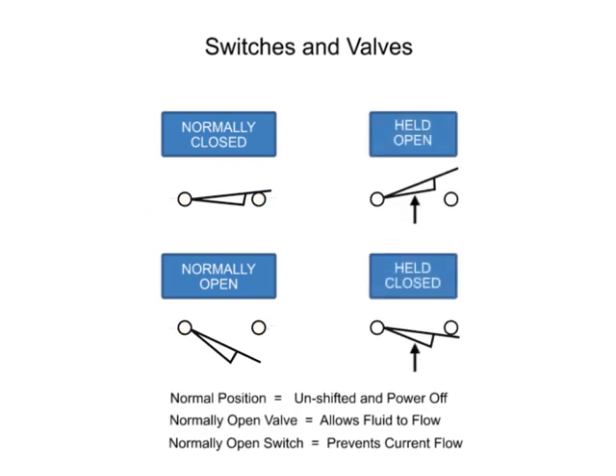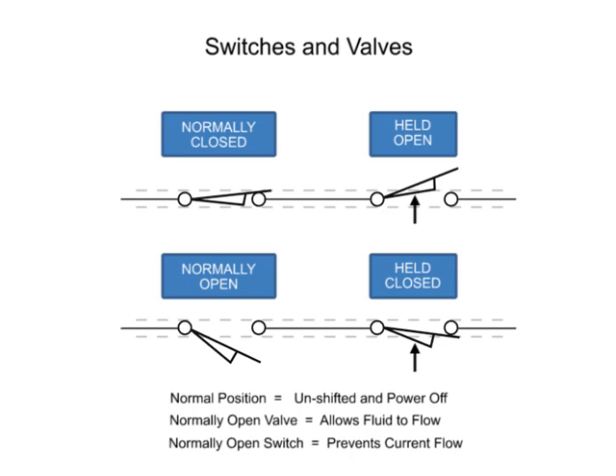Circuit diagrams are typically depicted in their normal off state before any work has been accomplished and no cycles have started. If the switch is drawn above the circuit line, it is a normally closed switch. If the switch is drawn below the line, it is normally open.